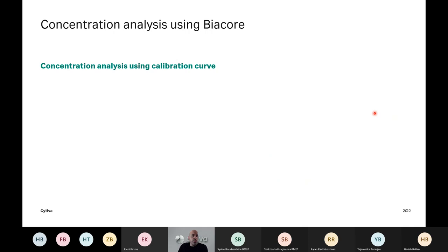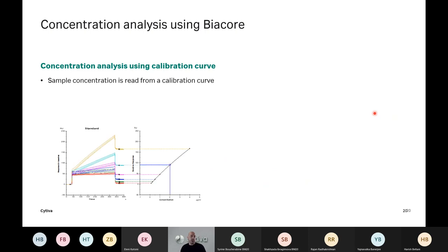So when we think about concentration analysis in Biacore, we can run concentration analysis in the standard way, that is using a calibration curve. That means that in this case, we would need to have a standard molecule with known concentration. And then in the same way as we do with other techniques, we will prepare a series of dilutions of this standard molecule and inject into the system. Then we will record the binding response to the target molecule, and from this binding response of the different concentrations of the standard molecule, we can create a calibration curve. Then we can inject our sample with unknown concentration of analyte molecules, and just by monitoring the binding response, we can get to know the concentration of this molecule.